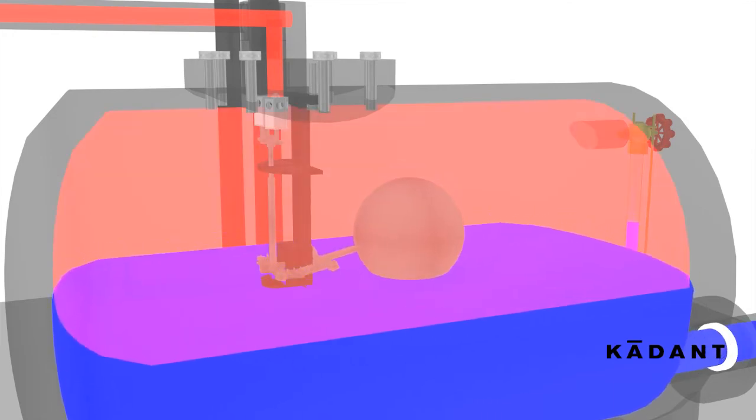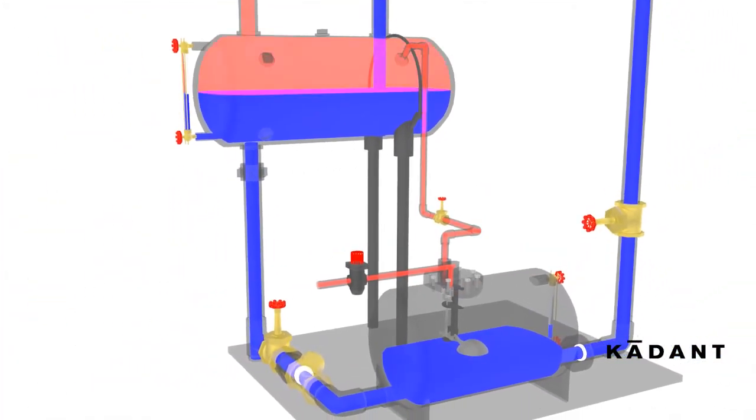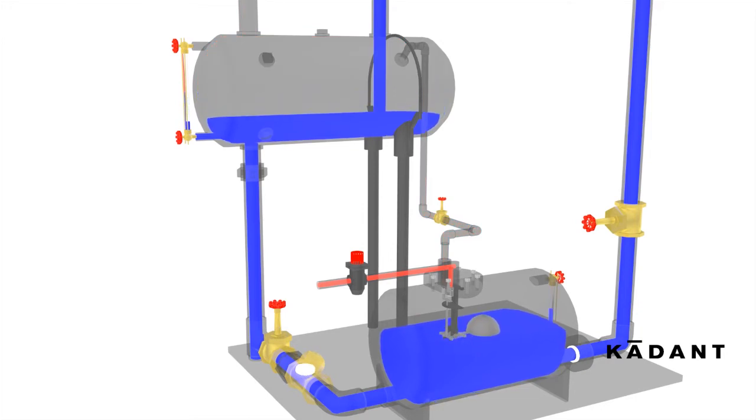the float mechanism snaps open the motive valve and closes the vent valve, allowing regulated motive pressure, steam, or compressed air to push the condensate out of the pump tank, through the outlet check valve, and into the overhead return line.